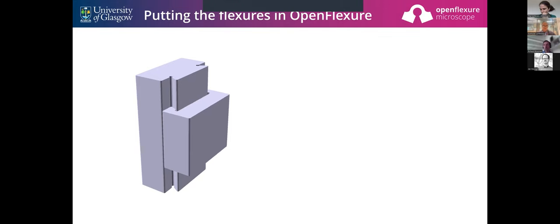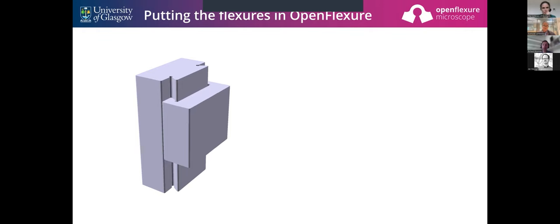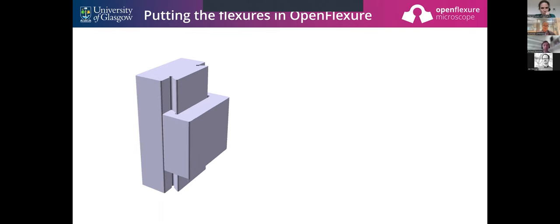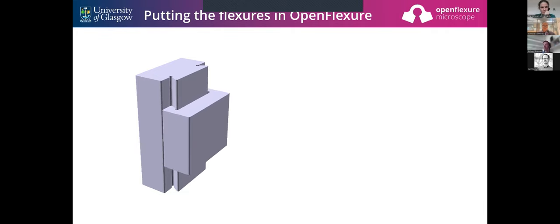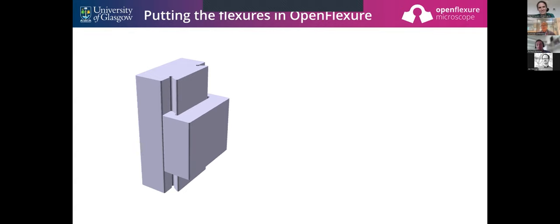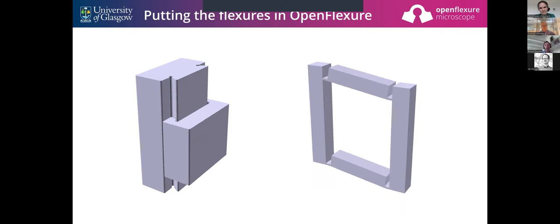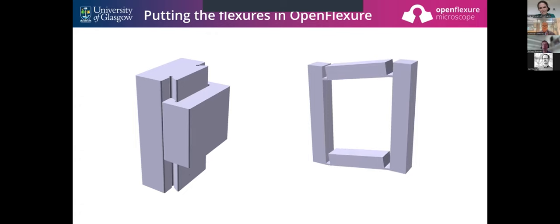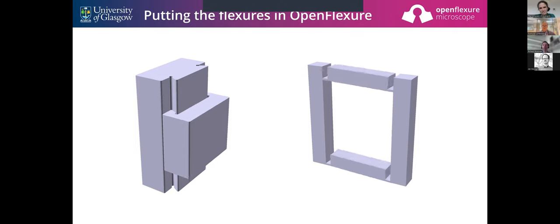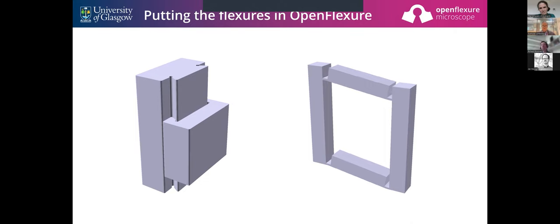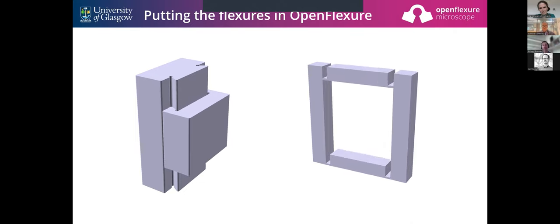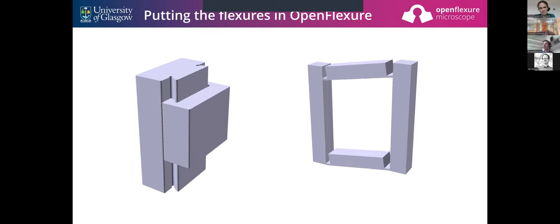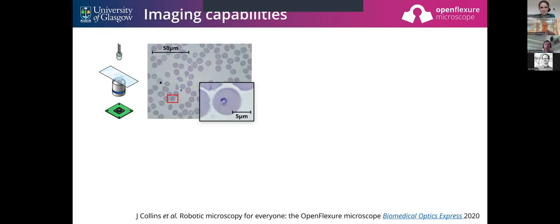The interesting innovation of the OpenFlexure microscope is mostly mechanical. In a conventional microscope you need to machine things very precisely — bits of metal that fit over each other and slide without wobbling. That's fundamentally quite expensive. If you try to 3D print a dovetail stage mechanism, it would be rubbish — trust me, I've done it. So the OpenFlexure microscope instead bends. Each of the thin bits in this parallelogram mechanism is like the lid on your shampoo bottle. Because plastic is softer than metal, these plastic flexure mechanisms are actually a really good way to make the precision translation stage you need for a microscope.